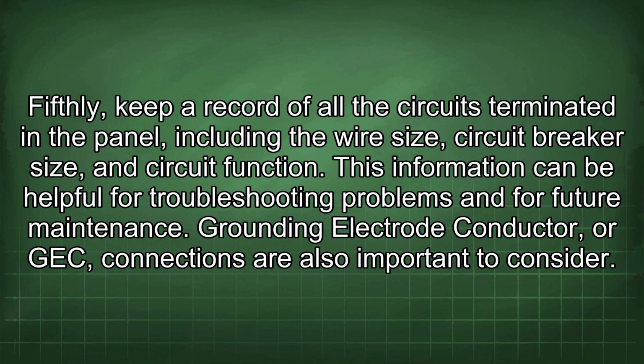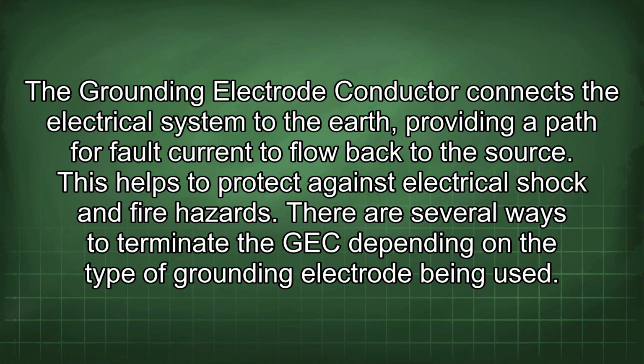Grounding electrode conductor, or GEC, connections are also important to consider. The grounding electrode conductor connects the electrical system to the earth, providing a path for fault current to flow back to the source. This helps to protect against electrical shock and fire hazards. There are several ways to terminate the GEC depending on the type of grounding electrode being used.